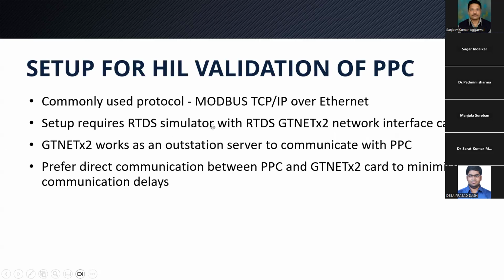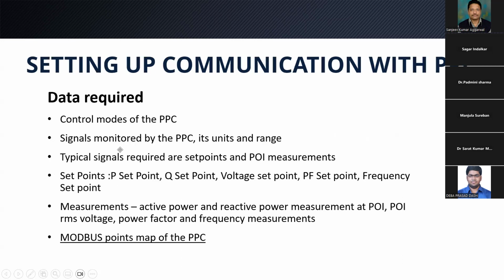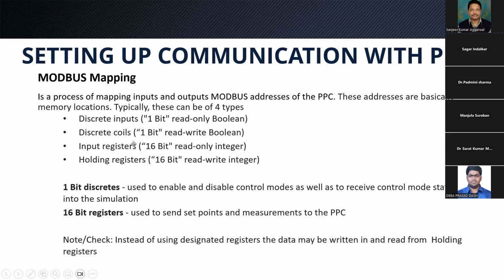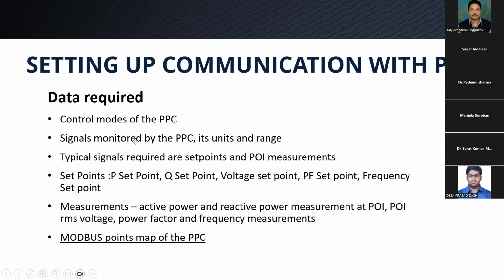So typically, you require an RTDS simulator to do that. Along with that, you require a communication card called a GTNET card, where we can install the Modbus protocol. It's a TCP/IP based, Ethernet based protocol. Then you need to know the input and output of the PPC, the measurement settings, and you also need to know the Modbus map of the physical PPC. Modbus map means the address where the set point should go and where it should come from. Right? So the addresses should be mapped.